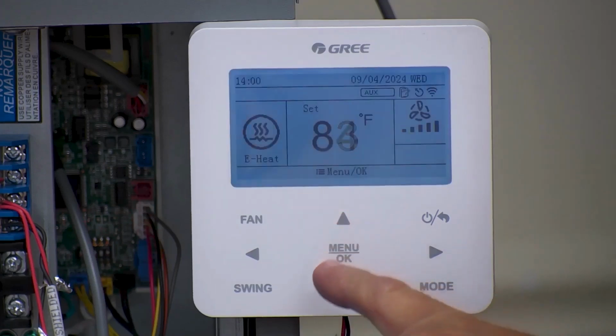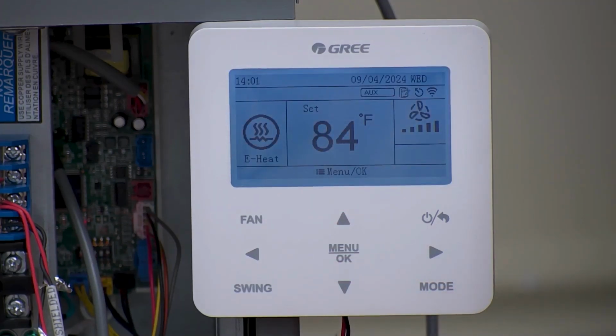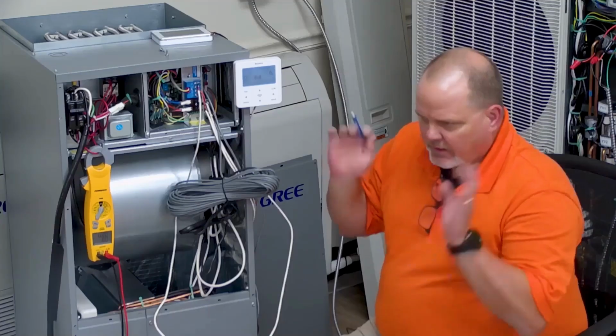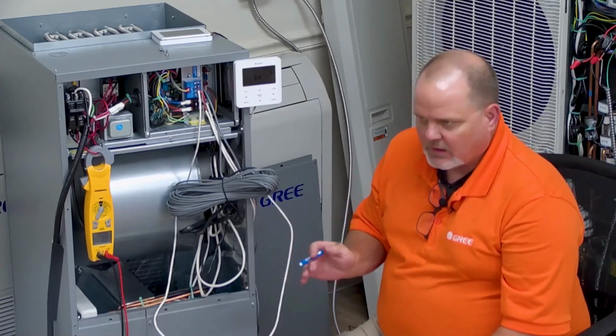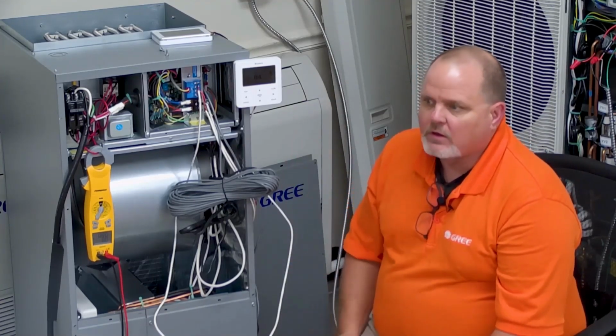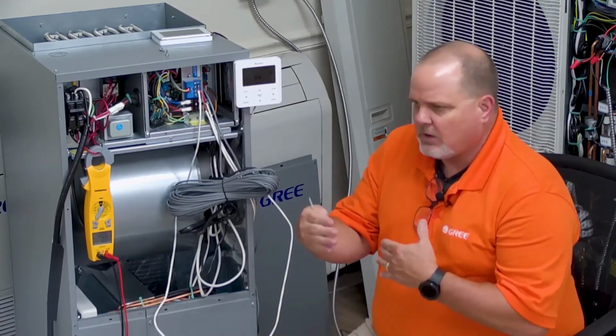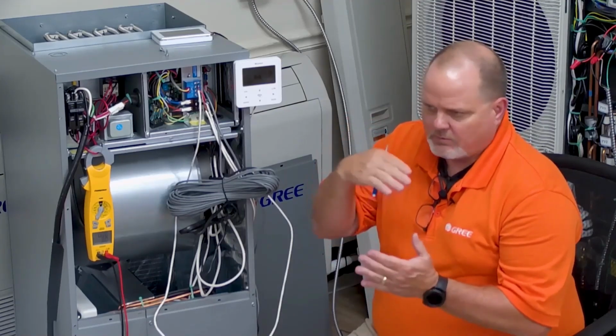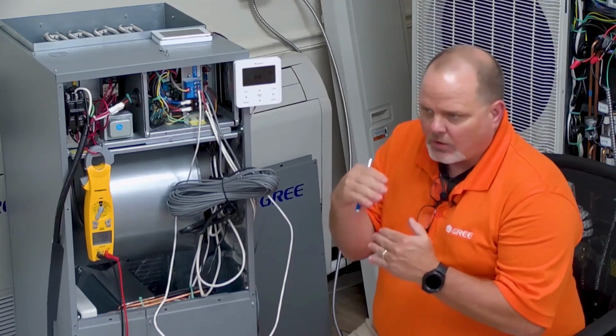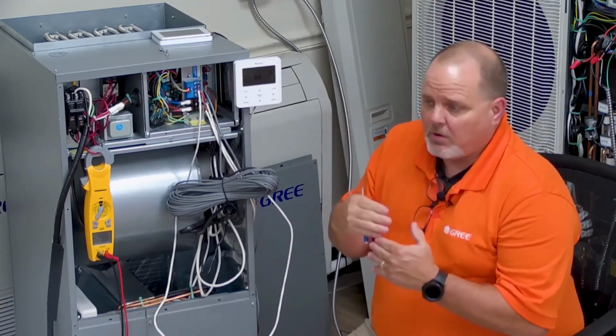So meanwhile, while I'm waiting on that, I'm going to kill the breaker. So as you can see, I just turned the power off to that MultiPRO unit this is hooked to. I'm still functional in the heat mode. So then also to kind of recap a little bit. If you don't have electric heat in the air handler, the controller will not recognize that it has electric heat. It will not let you say it has electric heat, and you cannot enable the E-heat mode. So you'll have a heat mode and E-heat mode. Heat mode would be heat pump, temperature differential. Once you meet your temperature differential and your timer, if you set a timer on there, then the auxiliary heat will come on with the heat pump.